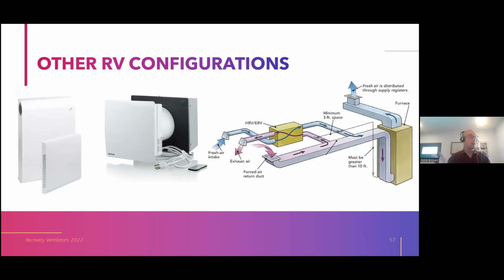Now, I talked mostly today about the dedicated distribution duct approach, which I would argue is best class, but there are other options. The model on the left is a through the wall unit. It's capable of small CFM, I want to say about 30 or 40. So you might need several of these for a house, but you don't need any ductwork.